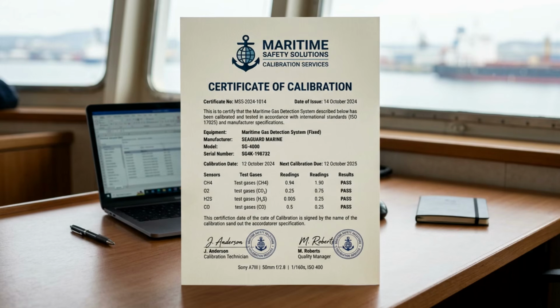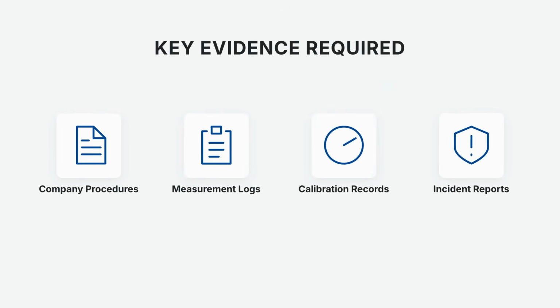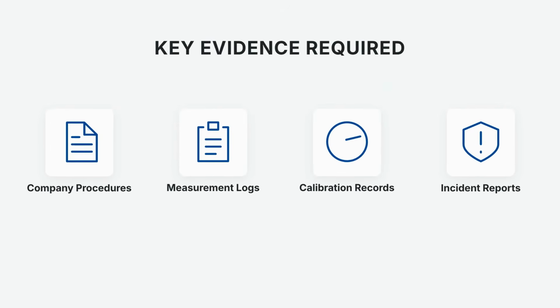Expect a detailed review of sensor calibration records to ensure they match company maintenance schedules. Key evidence includes company procedures, measurement logs, and system operation records. Incident investigation reports must be available if flammable gas was ever detected in void or ballast spaces.